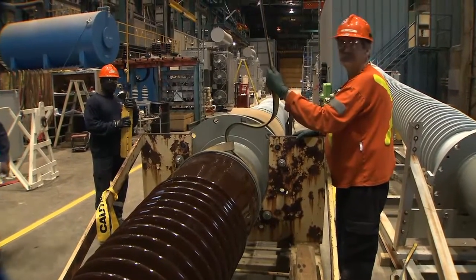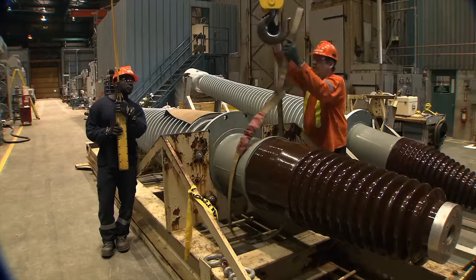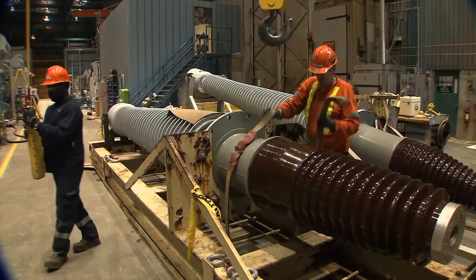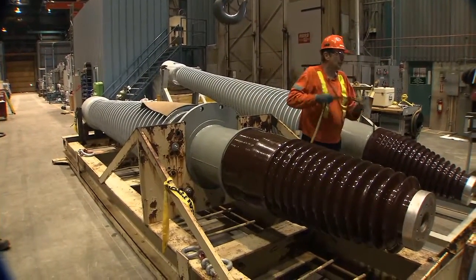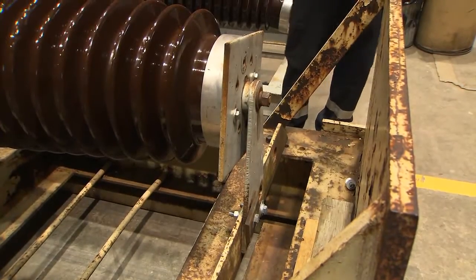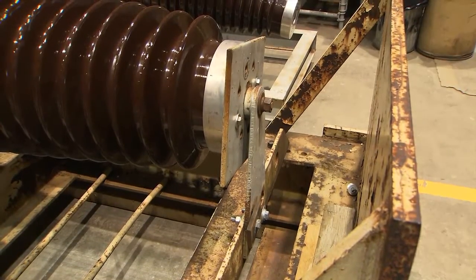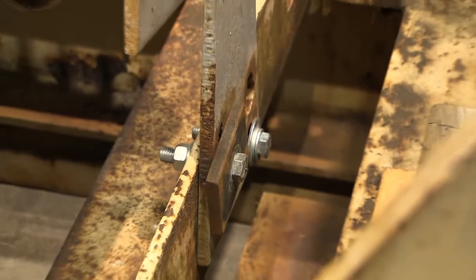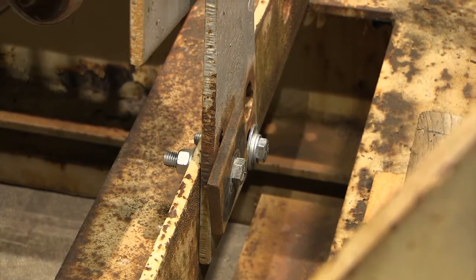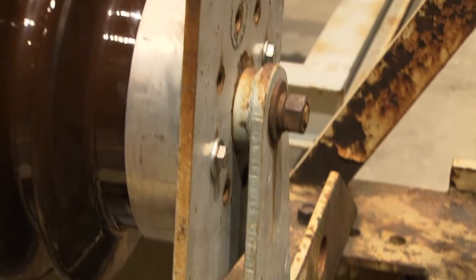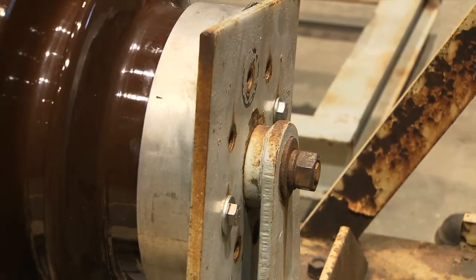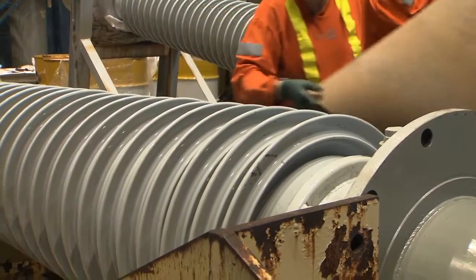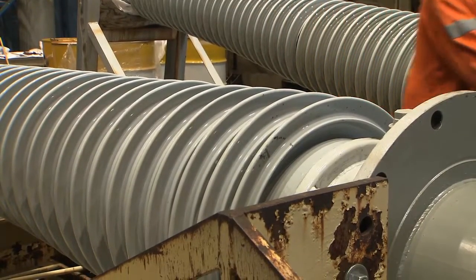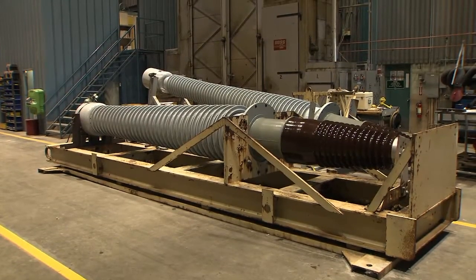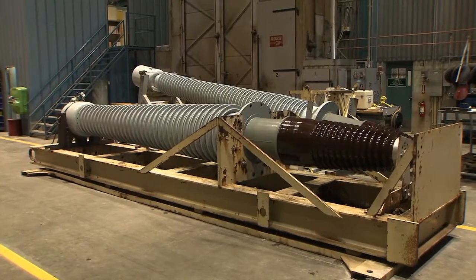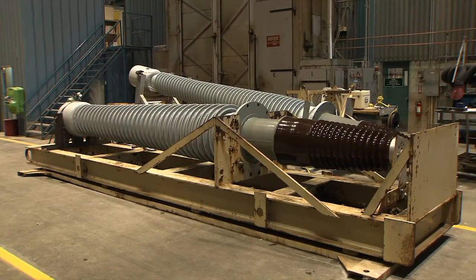Lower the hoist hook to just above the bushing. Remove the sling from the hoist hook and undo the choke around the ground sleeve of the bushing. Ensure the bolts are in place and secure where the metal arm is attached to the bottom flange of the bushing. Looks good. Remove the sheet of cork padding from the top of the porcelain. The refurbished bushing is now secure in the transport carrier and ready to be moved.